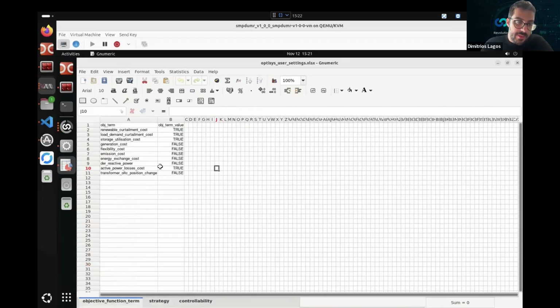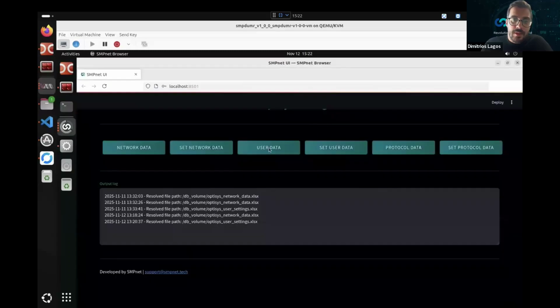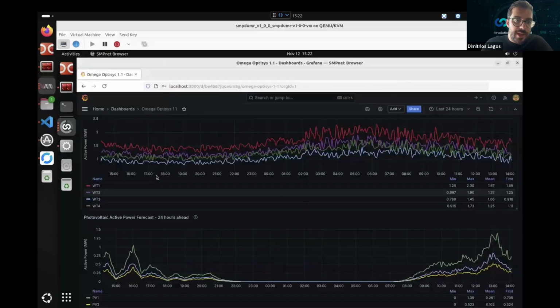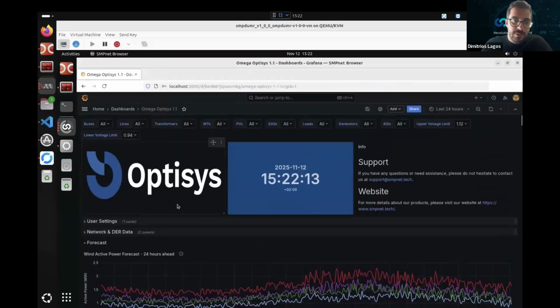So here, the user can select the different factors that should be taken into account by Optisys in calculating the optimal dispatch. For example, the curtailment of renewables, the curtailment of load. We have a storage in this model, so the utilization of storage, active power losses, tap changes in the transformer, and so on. Apart from this user interface, we also have an active dashboard. You see here the active dashboard of Optisys, where the user can see the actual data calculated by Optisys, as well as the latest measurements.